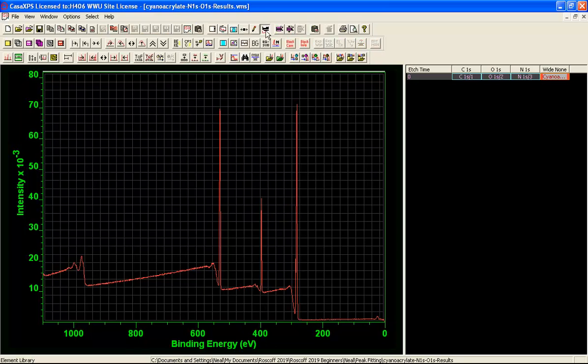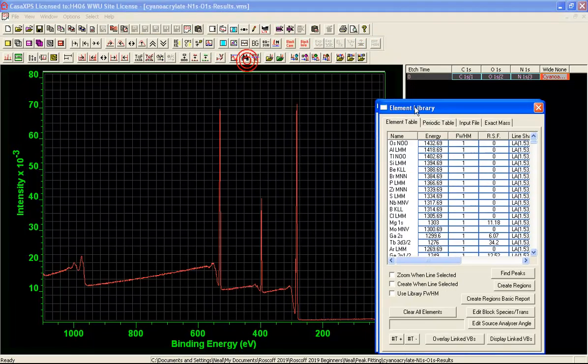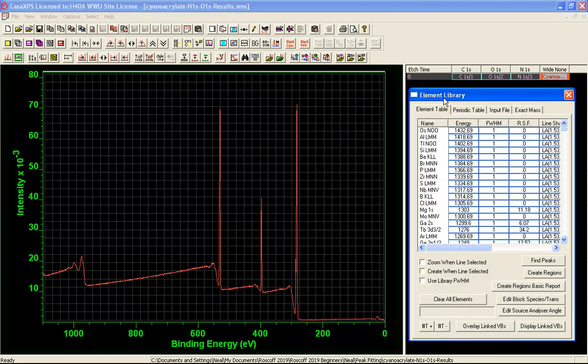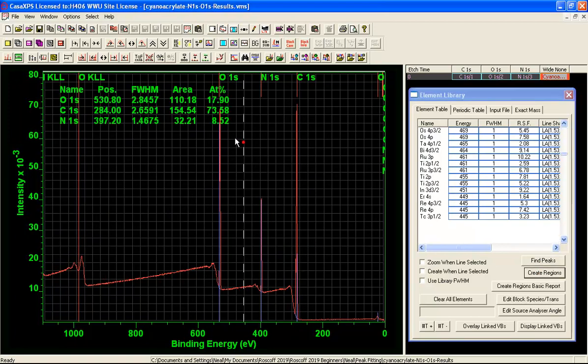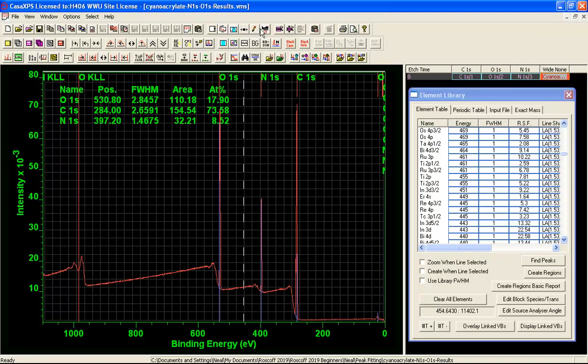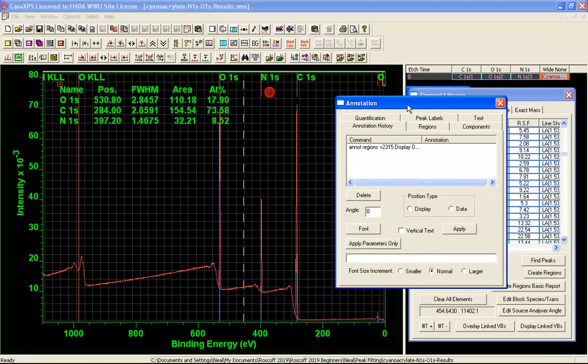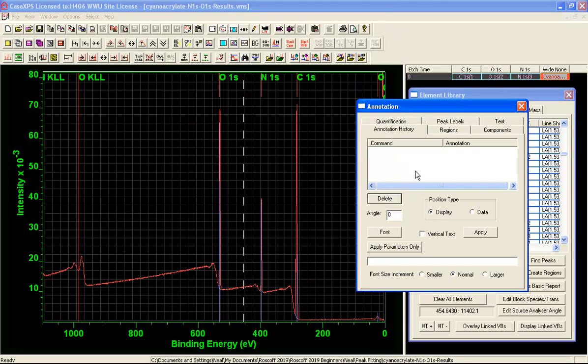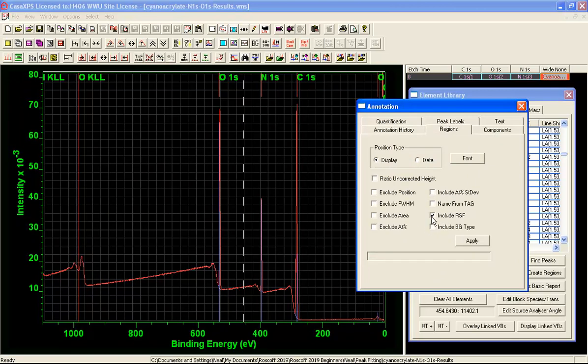So we can look at these by creating a quantification based on regions using the element library. So we will find these peaks and we can create, but I am not going to use the default region table because I would like to illustrate a little bit more than the quantification here. So I am going to go to the regions property page having deleted the automatically created table and I am going to add a table that includes the relative sensitivity factors.